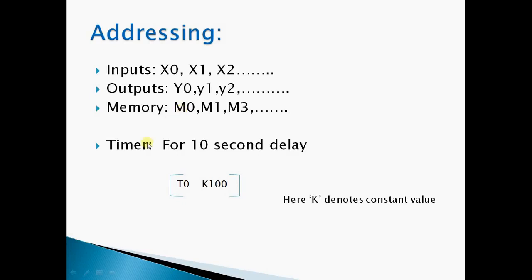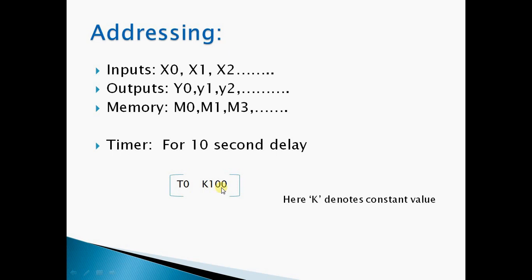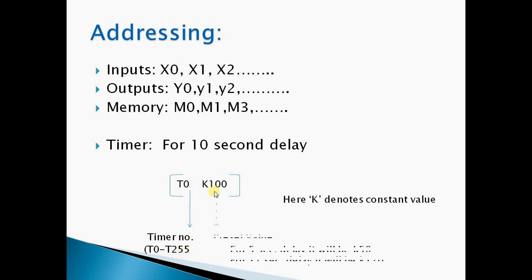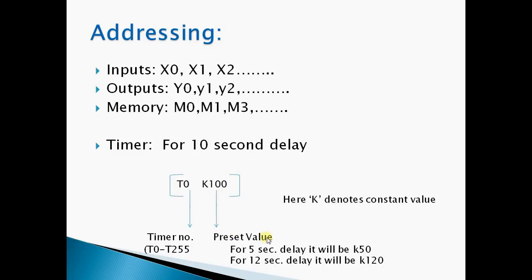If you want to program Mitsubishi PLC using a timer, the syntax is T0 space K100. Here T0 represents the timer number, which can be from T0 to T255. K100 represents the preset value. For 5 second delay it will be K50, for 12 second delay it will be K120. Here K denotes constant value.